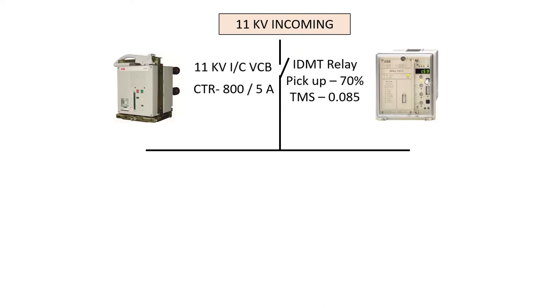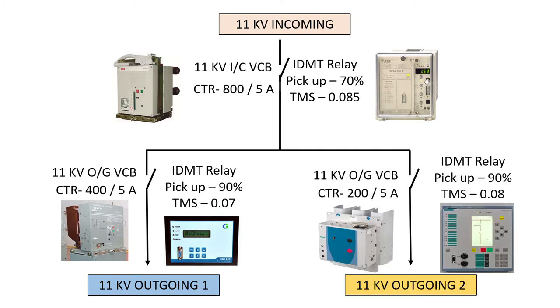Now we have added more details to this SLD that are found practically, such as current transformer specifications and relay types and settings. The relay we have selected is IDMT type. If you want to understand relay types, I'll have to make a separate video. If you want, please mention it in the comment section.